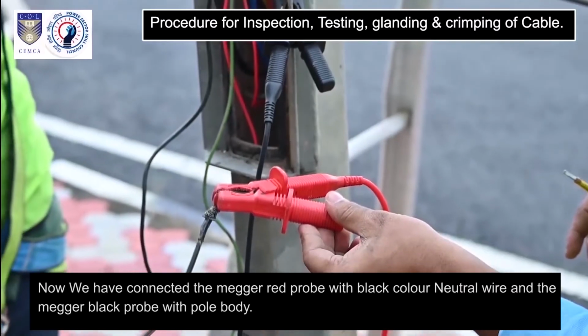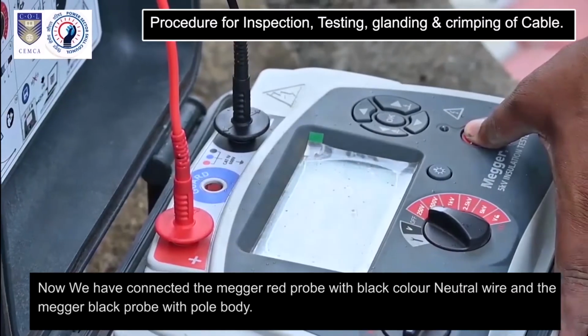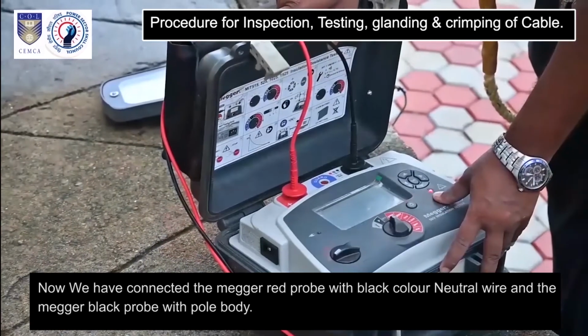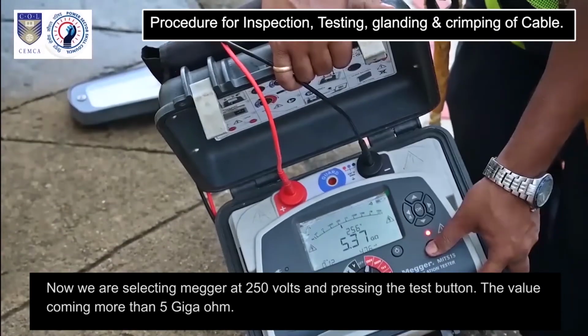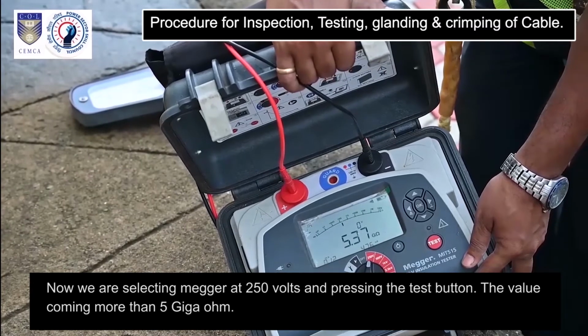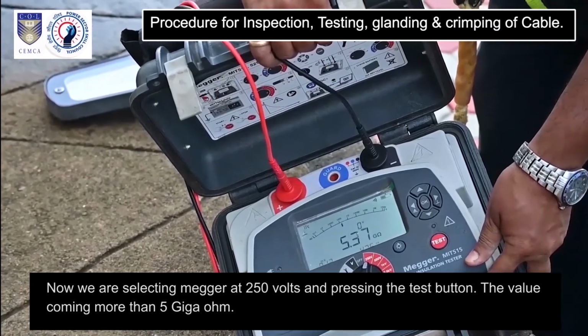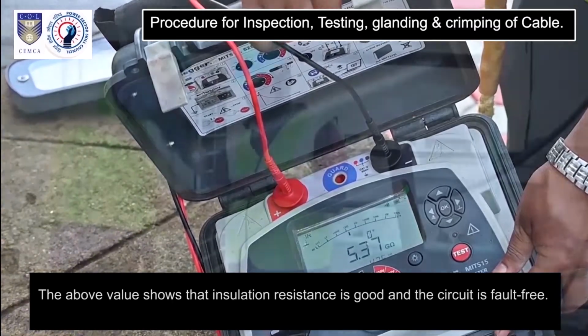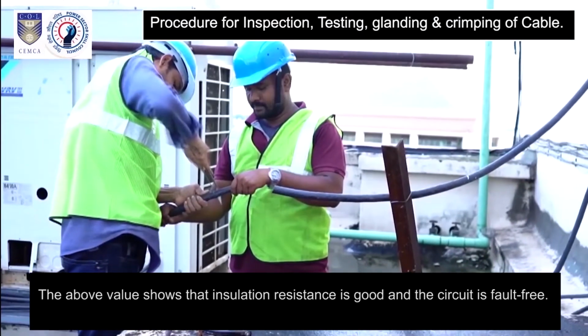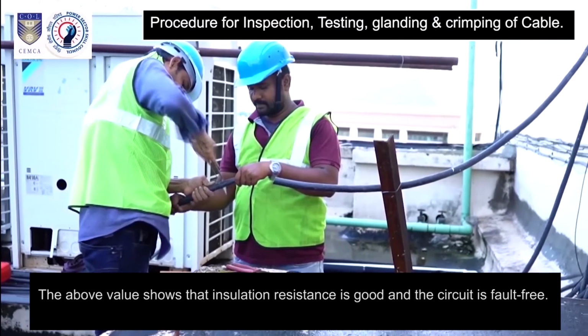Now we have connected the Megger red probe with black color neutral wire and the Megger black probe with pole body. Now we are selecting Megger at 250 volts and pressing the test button. The value coming more than 5 gigaohm. The above value shows that insulation resistance is good and the circuit is fault free.